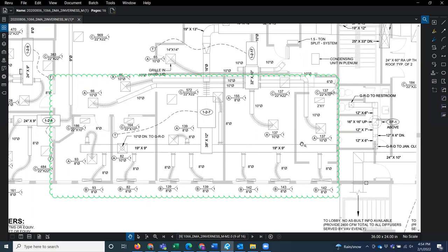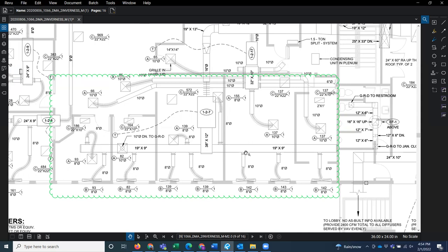Now, based on how many cubicles are fed from the single VAV, we might also suggest adding more thermostats to this VAV and averaging the temperature across. And these corrective actions wouldn't necessarily be identified unless SkySpark helped us point them out.